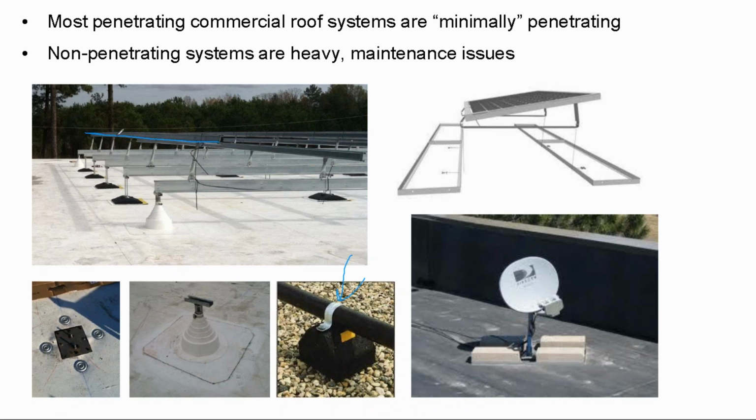So we say, well, we want to manage our cable, and so maybe putting it in conduit is better. So it comes out the edge of the array and then it goes into conduit rather than being strung from one row to the next. Well, that's okay, but are you having conduit coming out on every single row? Because sometimes these circuits have to be connected together. And so are you stringing cables under the array until you get to an exit point and then bringing them out in conduit? Cable tray is a little bit more flexible than conduit, so you can really bring all the conductors into it as you go from row to row.